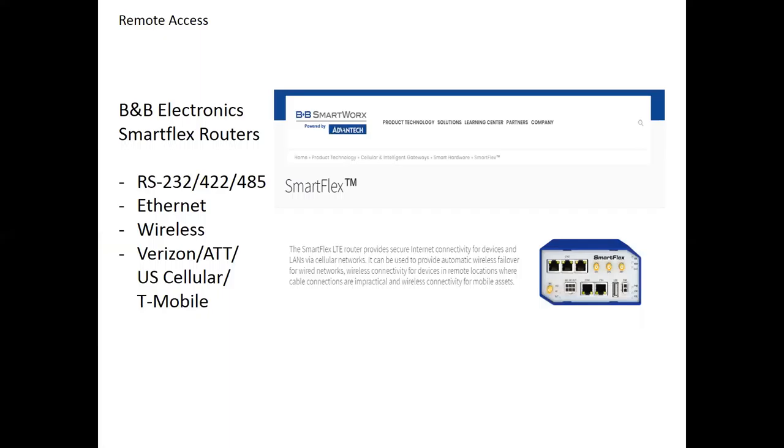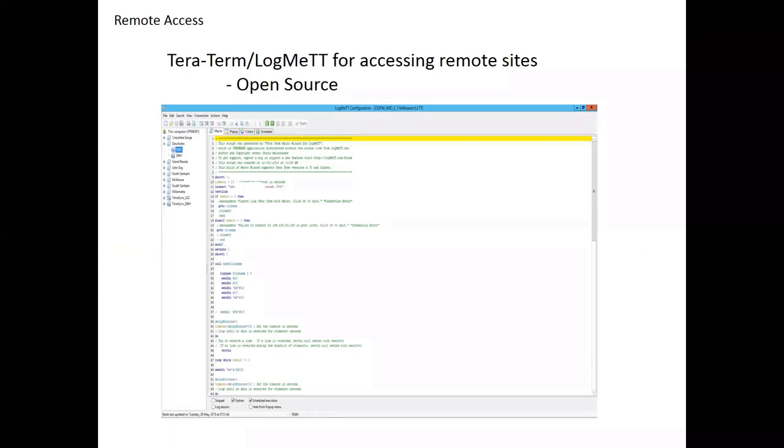How we get most of the data off these sites is by dialing into those modems. We use open-source software called TeraTerm and LogMeTT, which we run on a remote server. A script runs on a schedule — LogMeTT is great because you get a scheduler built in with the script. It runs as a system icon in the background, always running as long as the server is on. What we typically do is download all the tags and make sure we've got the data we really want. We use our test tags as the major diagnostic for all of our sites — that's a big deal because it tells us if the site is running and when it's running.